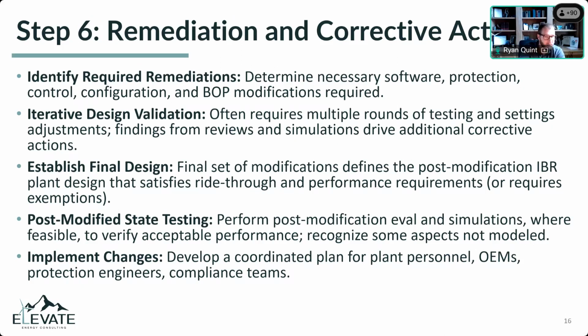That can be a simple exercise or an extremely complicated one. We don't necessarily have this in the document, but from practical experience there are a lot of model limitations. For example, we see the plant is fully compliant, but it's not meeting the 1 second active power recovery, even though the OEM documentation says it should recover within 1 second. So is it actually compliant, or is it some weird model issue?